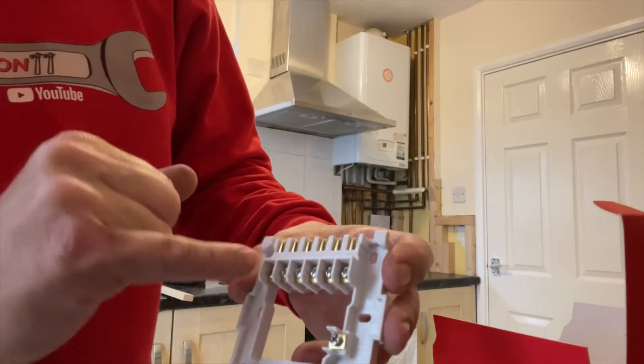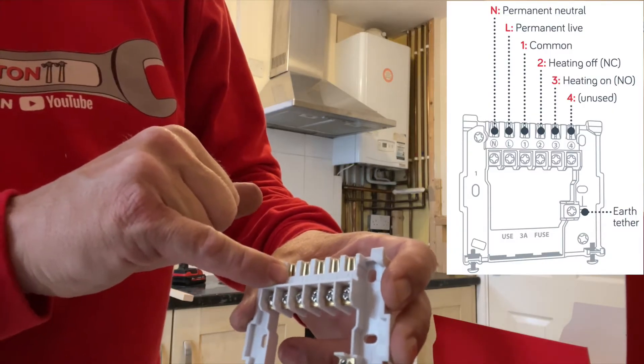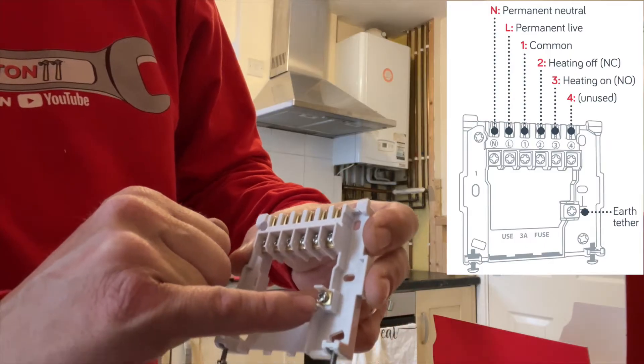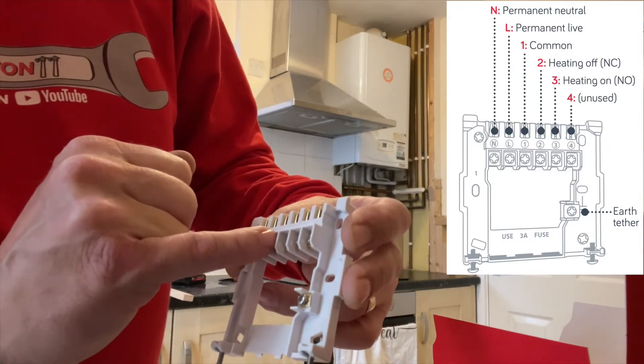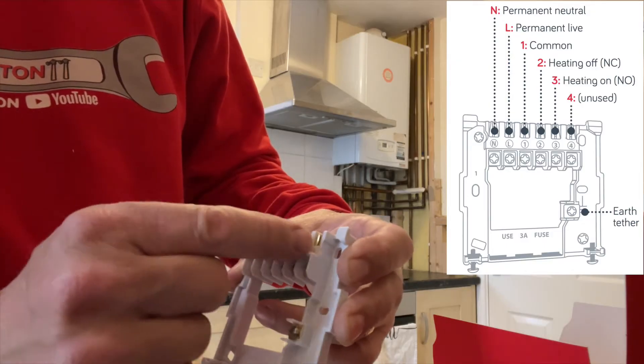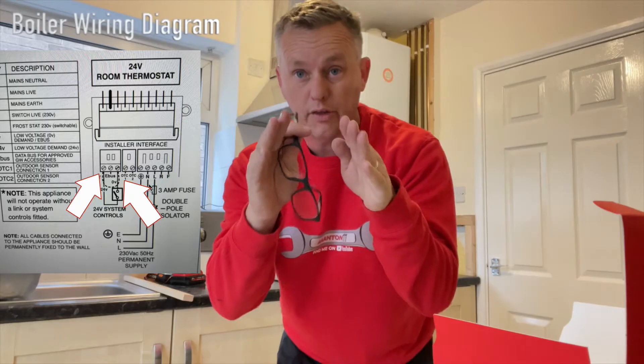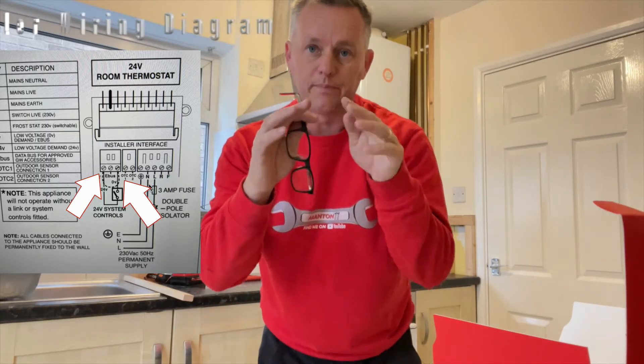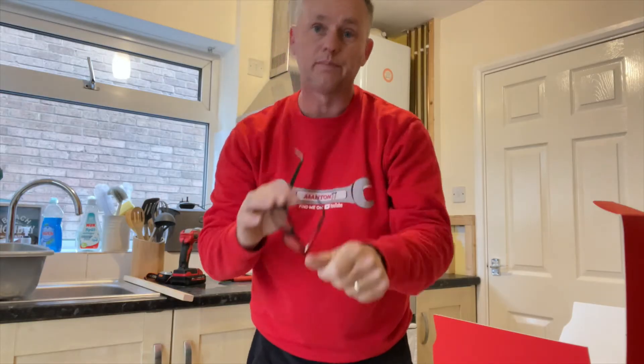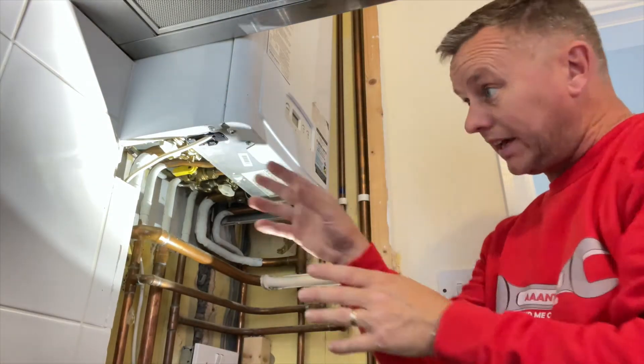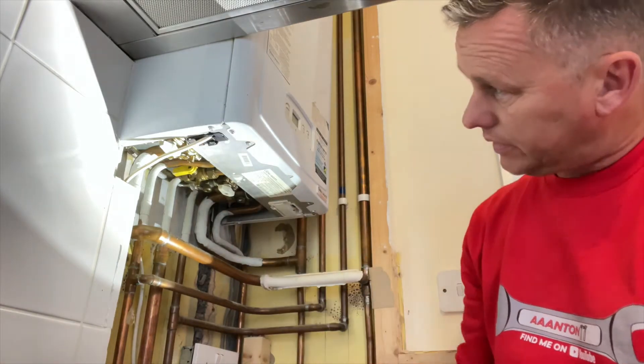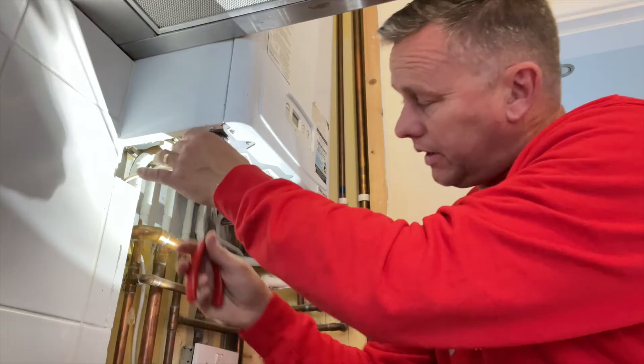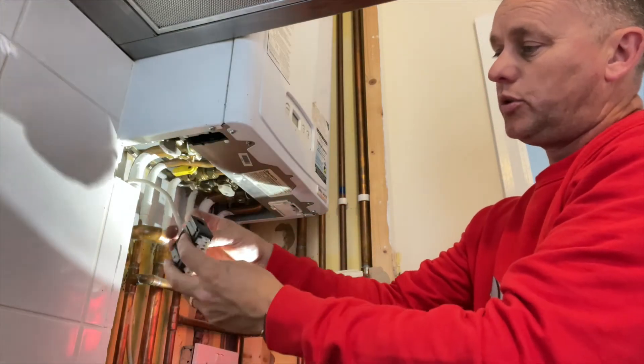All we're interested in is neutral, blue, brown for live, the earth wire which is going to go over here, and then we're going to use the one and the three. We're only using one and three. Now the one and three are the thermostat break in the boiler. There's a little jumper wire that we're going to take out and put one and three to those two terminals. On this boiler, it's got a little tab. You pull down and it reveals the little power box here.